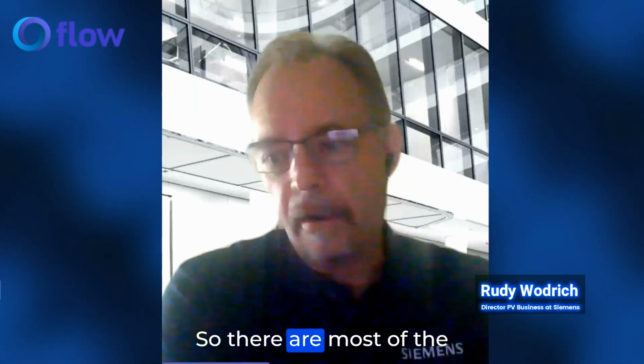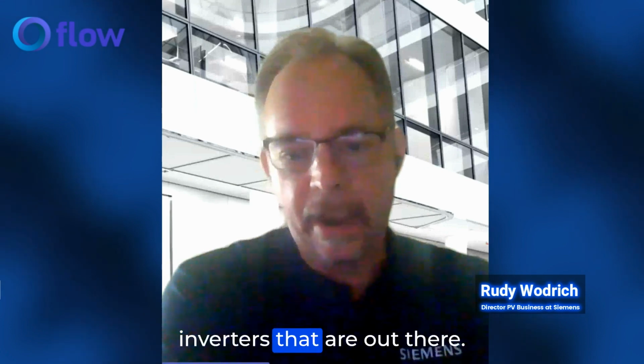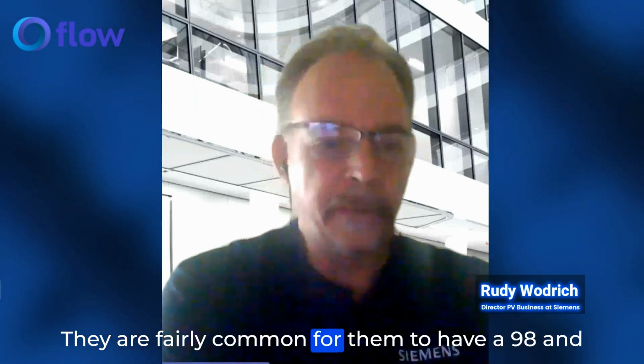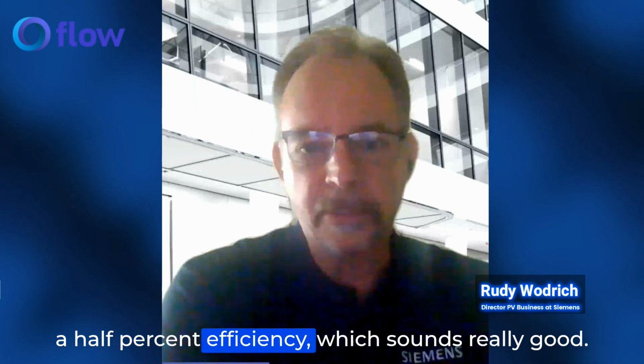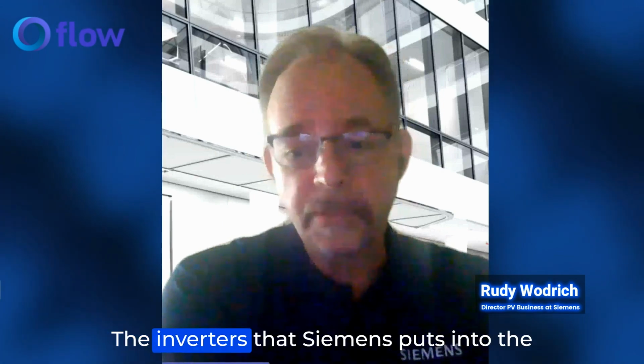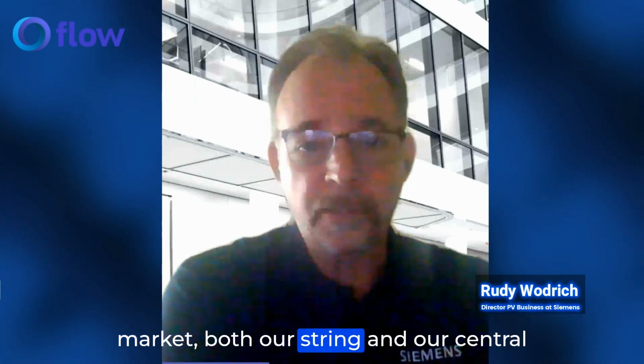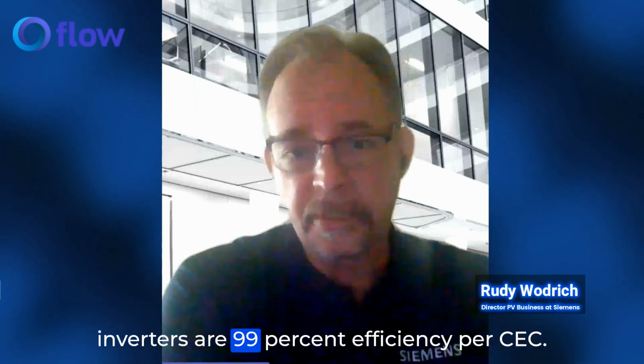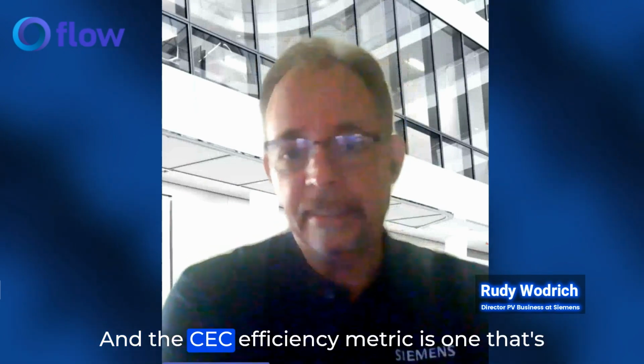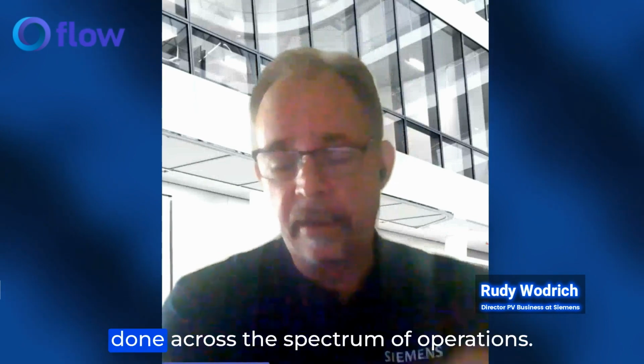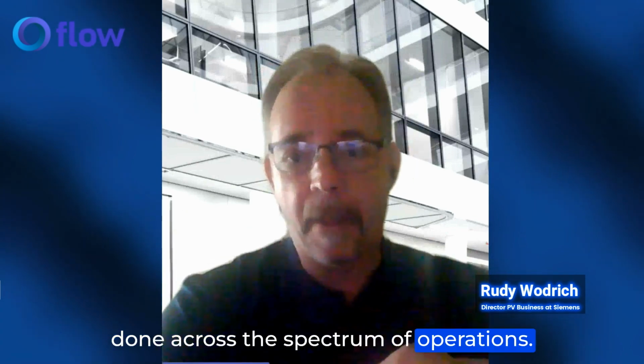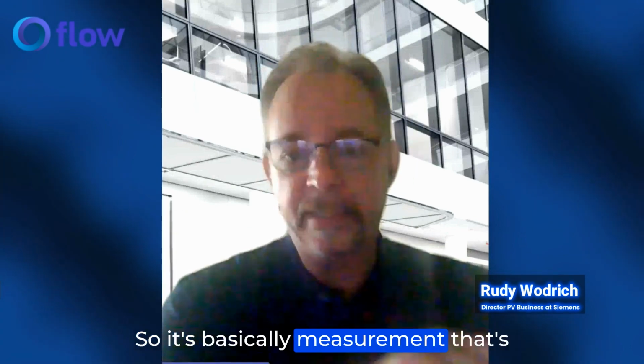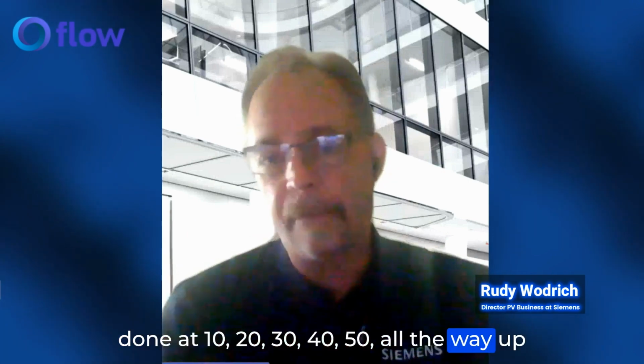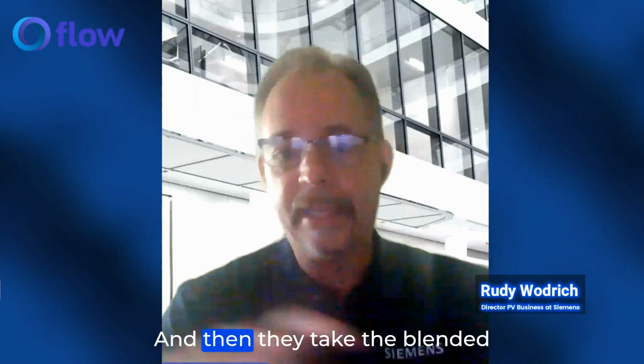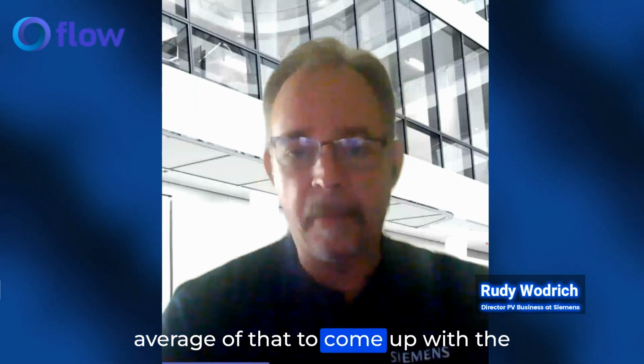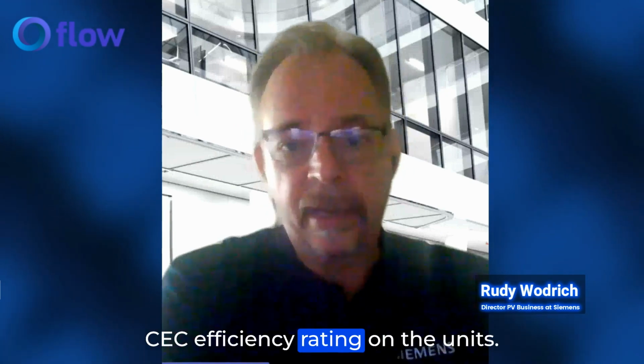Most inverters on the market commonly have 98.5% efficiency, which sounds really good. The inverters that Siemens puts into the market, both our string and central inverters, are 99% efficiency per CEC. The CEC efficiency metric is measured across the spectrum of operation—at 10, 20, 30, 40, 50, all the way up to 100% output power—and then they take the blended average to come up with the CEC efficiency rating on the units.